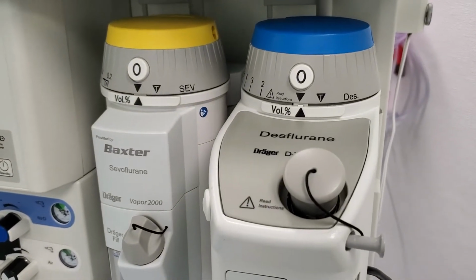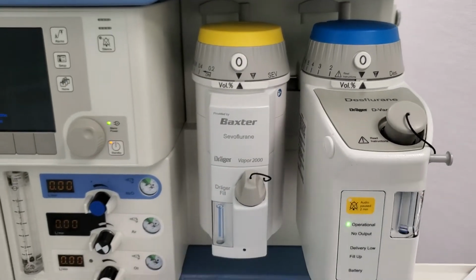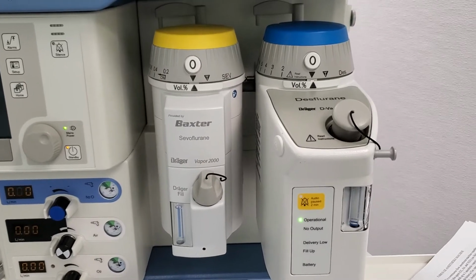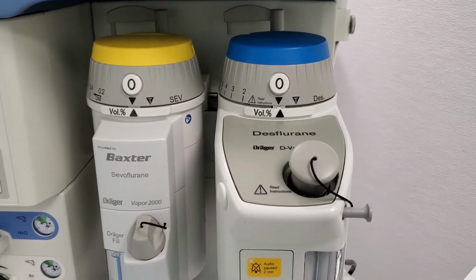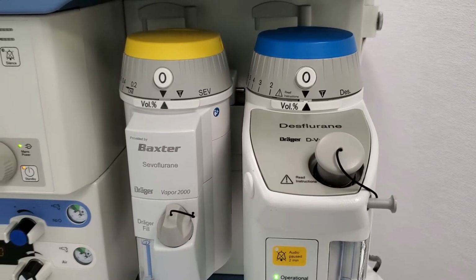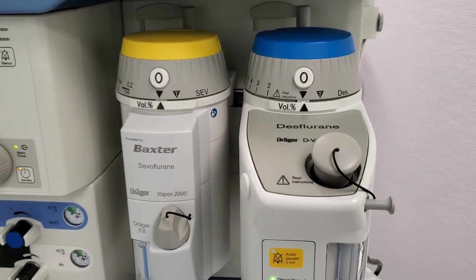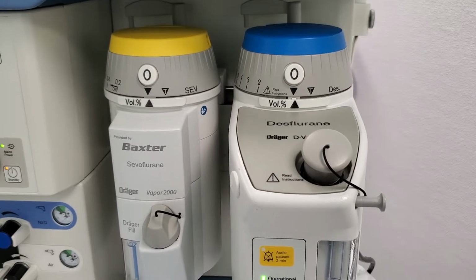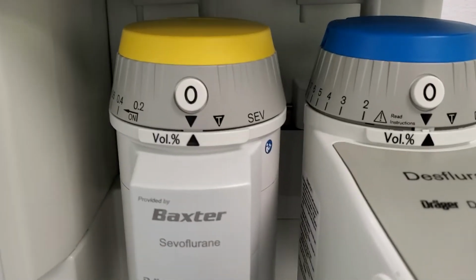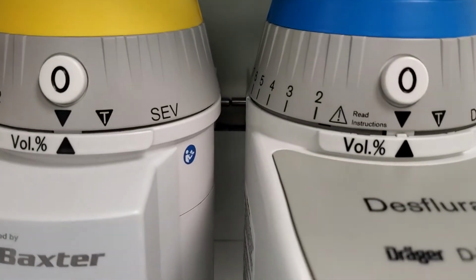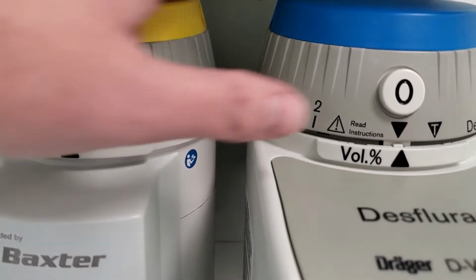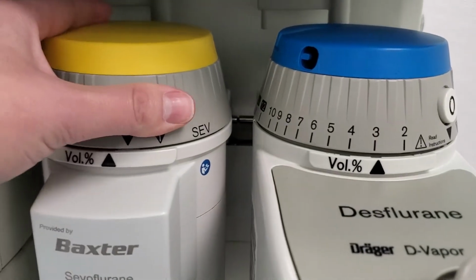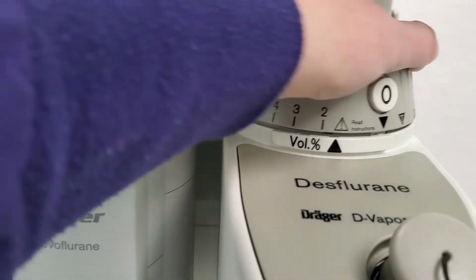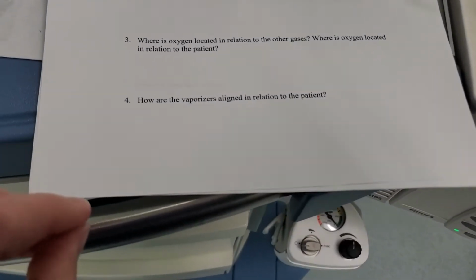How are the vaporizers aligned? Well, again, we need to have the most potent closest to the patient. So same kind of idea. We don't want a leak developing between the vaporizers so that a more potent gas could potentially contaminate a less potent vaporizer. The vaporizer interlock device prevents us from turning more than one vaporizer on at a time. So there's pins. It pushes forward so that I physically cannot turn on the other vaporizer. That's a safety feature of the vaporizer.